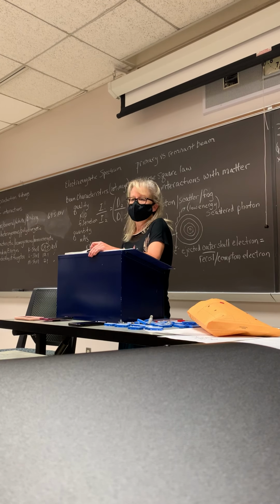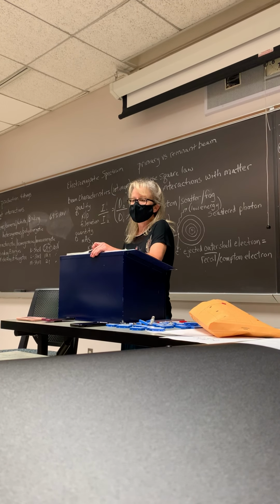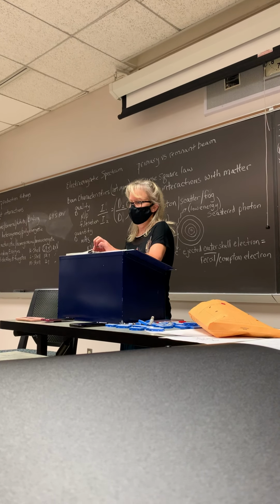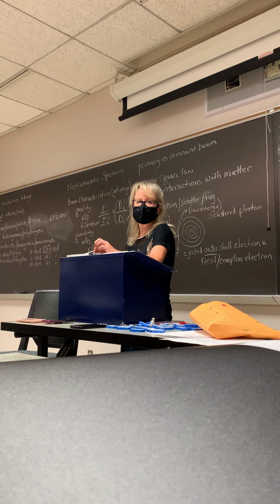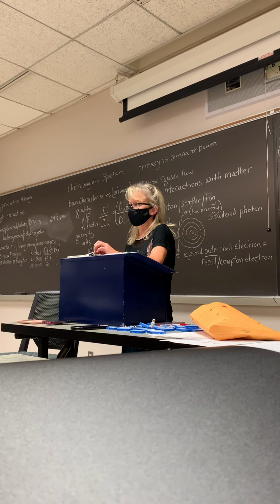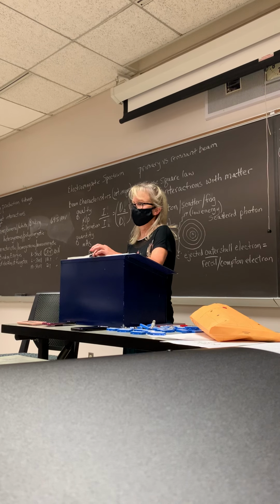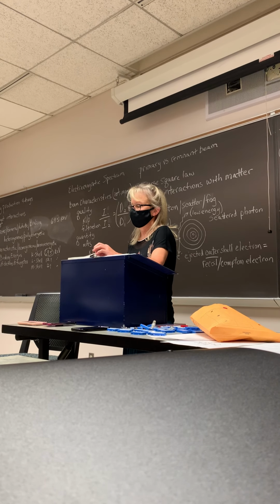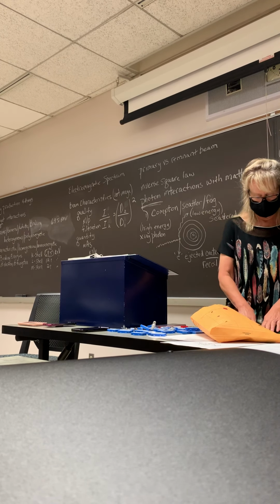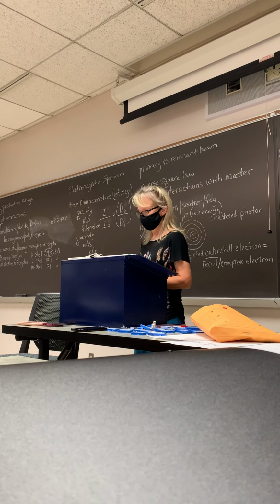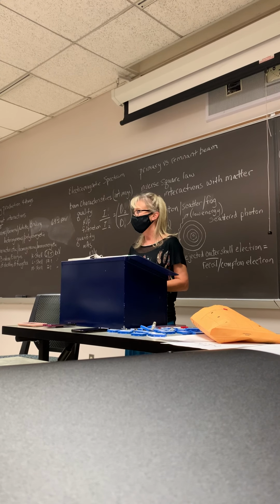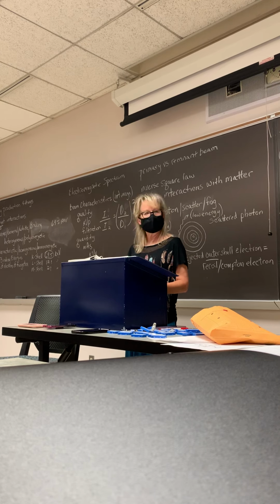Quantity of the beam refers to the number of photons, or intensity of the beam. What's the main factor for quantity? mAs. The main factor for quantity is mAs. The higher the mAs, the more photons produced. Quantity is also influenced by kVp. The higher the kVp, the more the quantity.